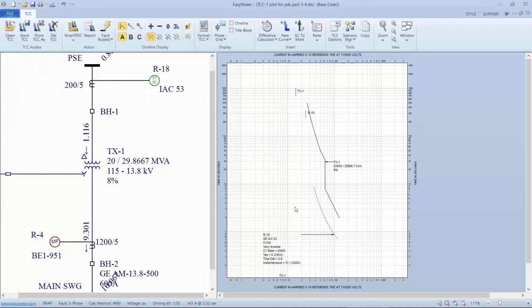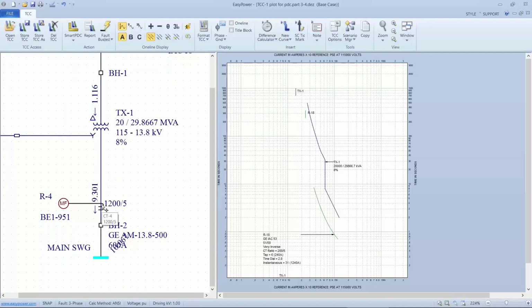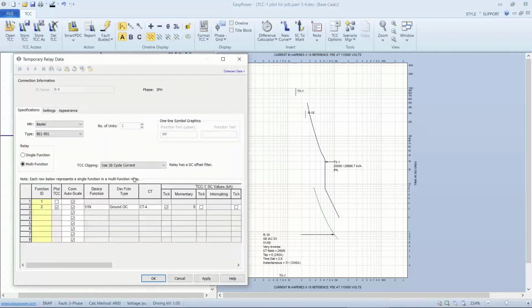Now, another point to be made is that this should be the slowest device in the system. So we want to coordinate everything downhill from that. All right, so that gives me a pretty good starting place for R18. Let's put R4 back in the mix. Open the dialog box. Now, when I deleted it off the TCC curve, the effect was to uncheck this box for the TCC plot. So let's check the box again.